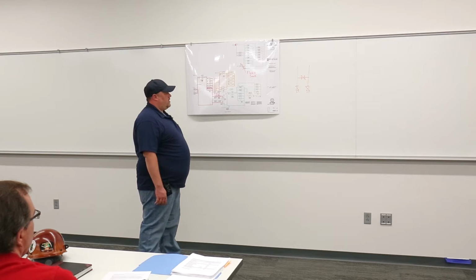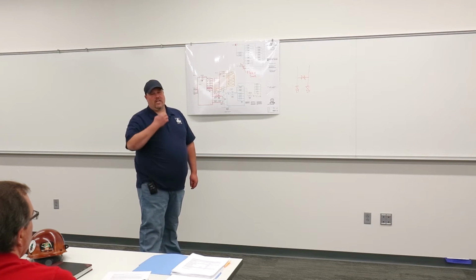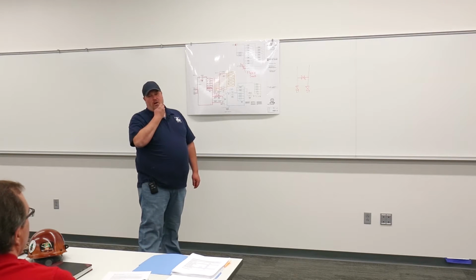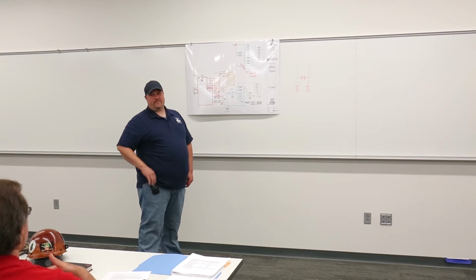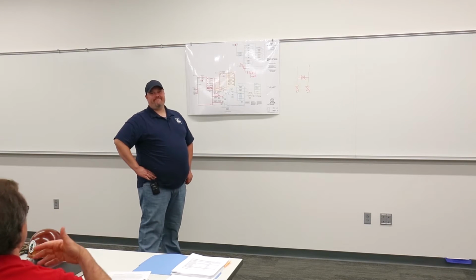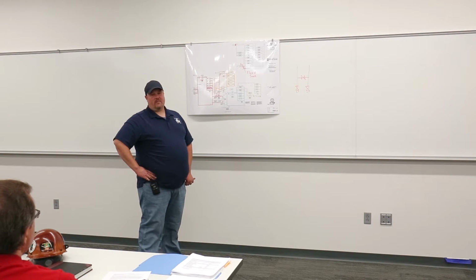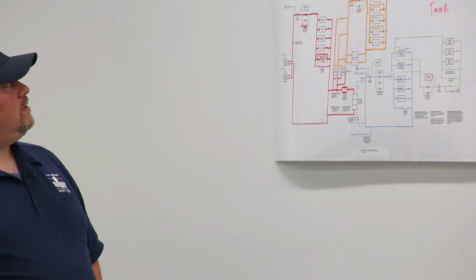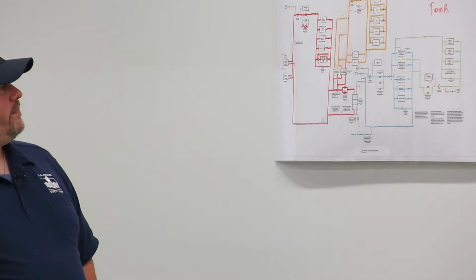Yeah, I mean, we've already had issues with that. I think they just fixed a leak in the glycol packs on one of the pumps. Yeah, any kind of maintenance, in the coils, in the pumps, it'll drain. The relief valves, and we've got it set up where all the relief valves in that system go back to the glycol feed tank. Right. Good. Okay. Good? All right, so we're ready to go to the field.